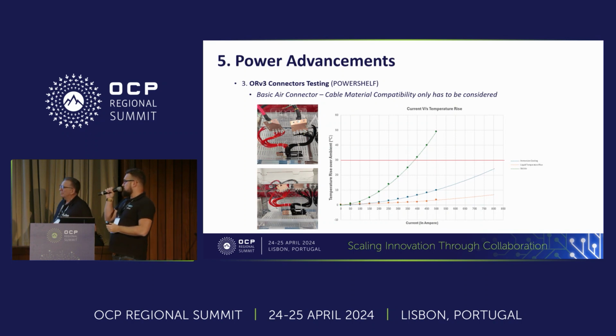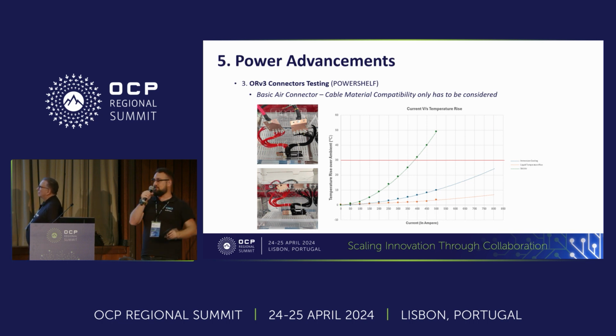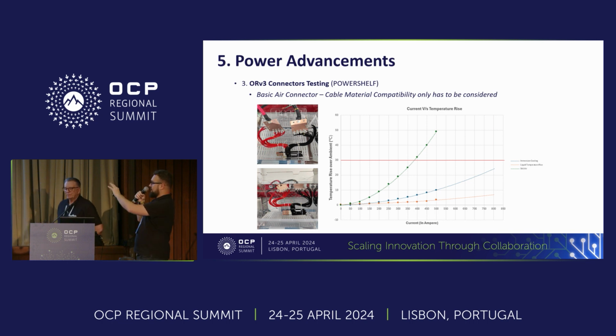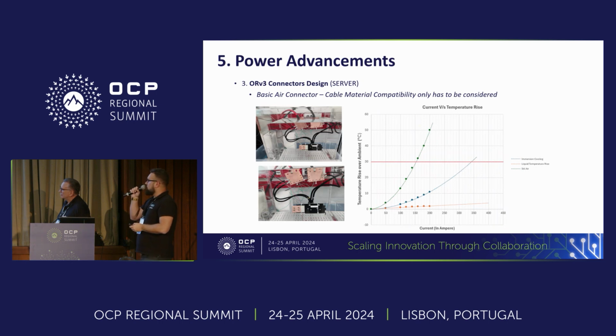Now going to the connectors, the graphs look very similar to each other, but trust me, they're from very different testing environments. This was carried out by Molex, as I mentioned before, and they've seen the connector suffering the same type of trend. In air, bringing a power shelf connector to 400-450 amps delivery results in a 50 Celsius increase, which is a lot. In immersion, the blue line shows that at 100 amps we're only at 20-25 Celsius increase, which at the bottom of a tank in immersion is more than fine to have. The same applies to the server connector - similar lines, similar situation.